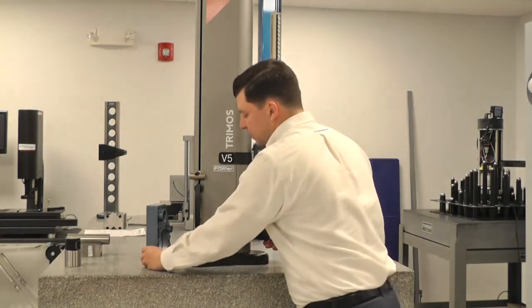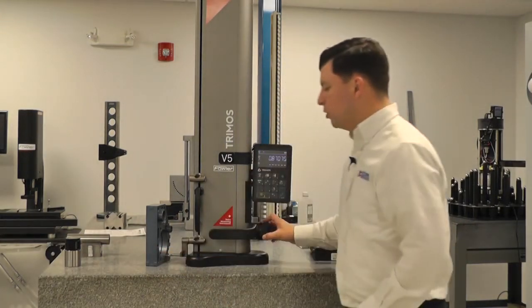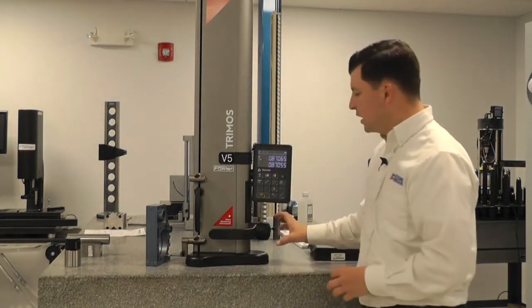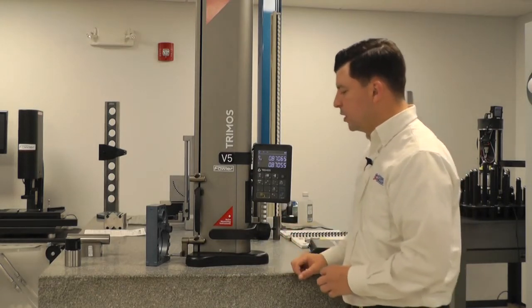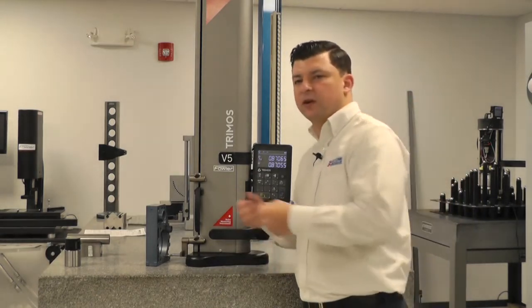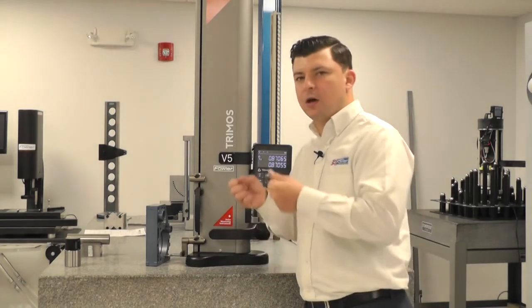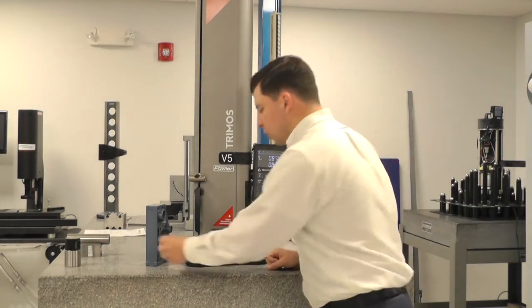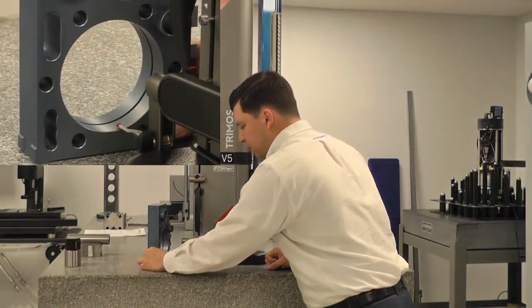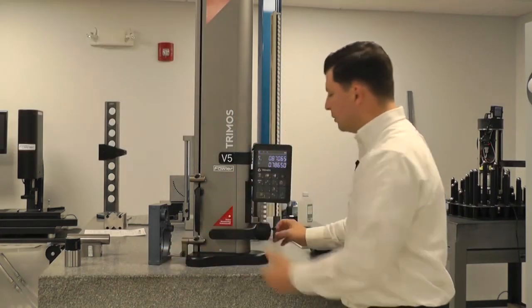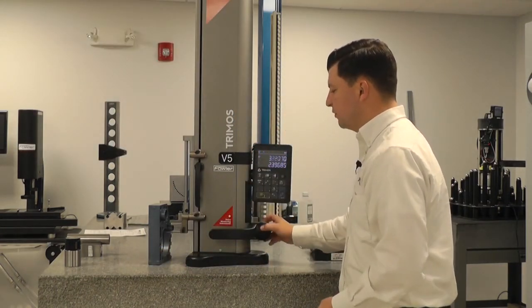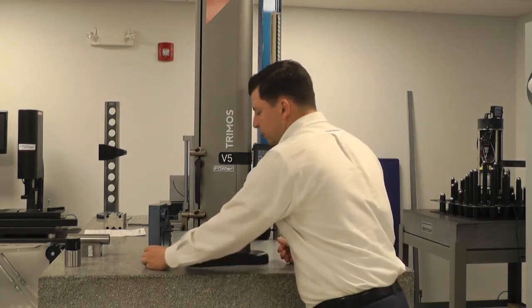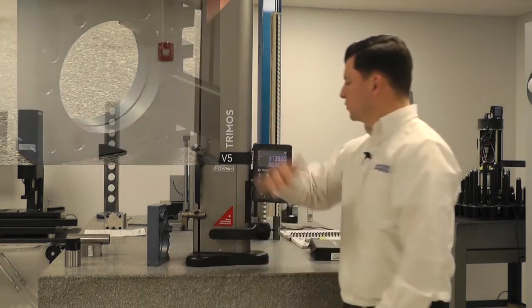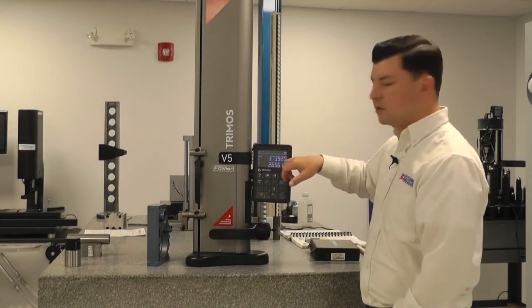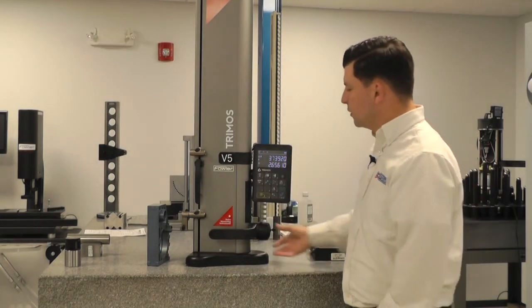The nice thing about this gauge is when I do engage the probe, I don't have to maintain any force or hold down any pressure. The gauge has a constant measuring force, so we're going to sit on that probe. We're going to allow it to maintain that constant force while we sweep our part through the bottom. And then we'll go ahead and replicate that on the top. So we'll drive it up to the top of our diameter, and then we'll sweep through the top. And once we pass that top point, once we find the reversal point in that high point, the gauge will give us our diameter and our center line.